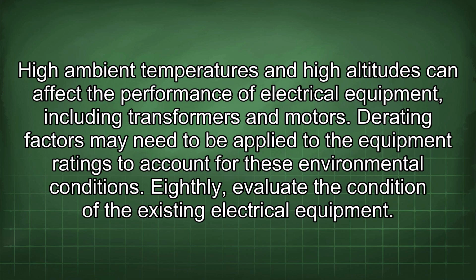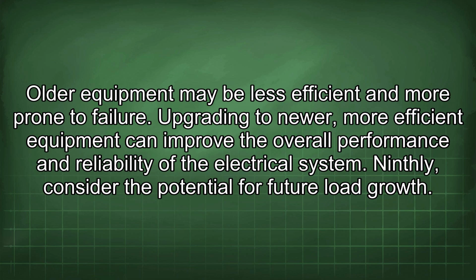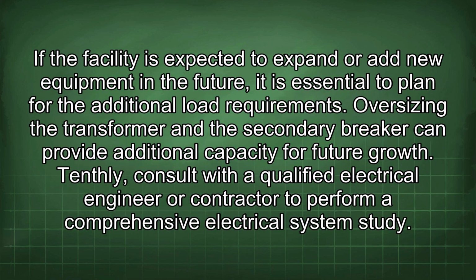Eighthly, evaluate the condition of the existing electrical equipment. Older equipment may be less efficient and more prone to failure. Upgrading to newer, more efficient equipment can improve the overall performance and reliability of the electrical system. Ninthly, consider the potential for future load growth. If the facility is expected to expand or add new equipment in the future, it is essential to plan for the additional load requirements. Oversizing the transformer and the secondary breaker can provide additional capacity for future growth.